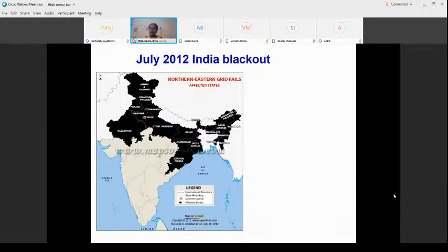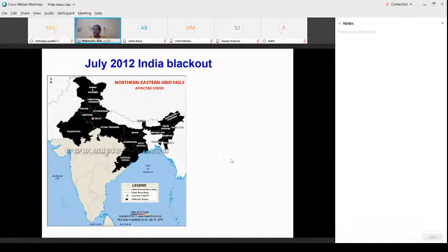So this line was overloaded, and that concept, you can write it in your notes, we call the load encroachment problem. So when some line is overloaded, we call it the load encroachment problem, and the relays which protect the line, one of the major devices being the distance relay, maloperated due to the load encroachment problem. Zone 3, you can write it. And if you need more detail, I can send some PDF files for this, and there you can see a picture of how it happened. So when that protective device maloperated due to the increase in the load through that particular line, the line tripped. The breaker was open, the line was open, out of service.